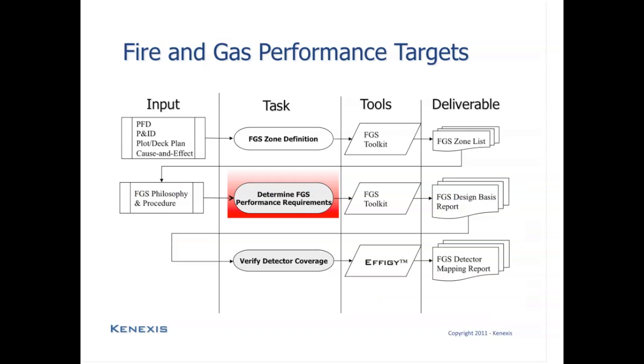After the FGS zone list is completed, the next step in the performance-based FGS design is going to be to determine the FGS performance requirements. And the FGS performance requirements is going to be performed using the FGS zone list to tell you which zones you need to set a performance requirement for, and also the procedures coming from the FGS philosophy that will set procedures, requirements, and also tables and tools for selecting what the performance requirements should be. Again, we would recommend that you use some type of automated database toolkit to perform this task with the philosophy rules built into the database. And the ultimate result will be a fire and gas system design basis report and performance requirement selection worksheet tables specifically.